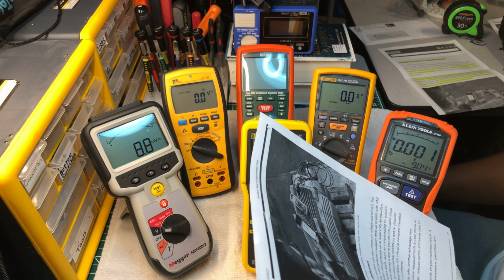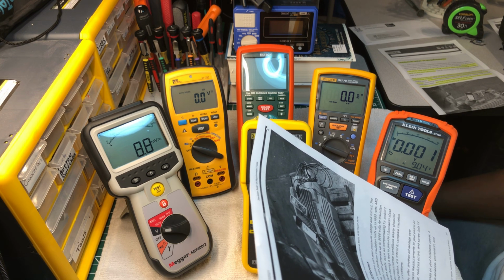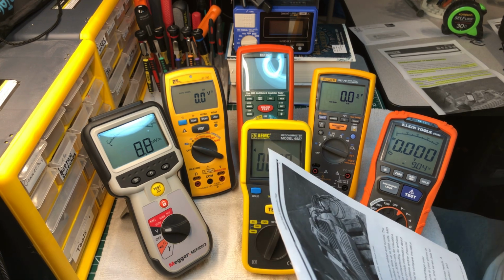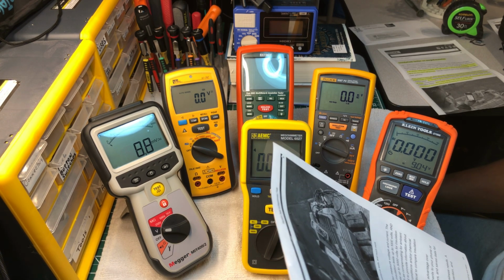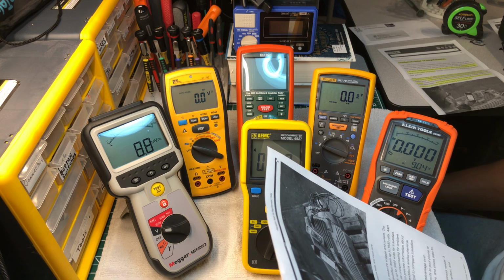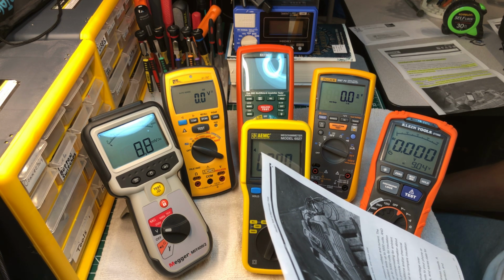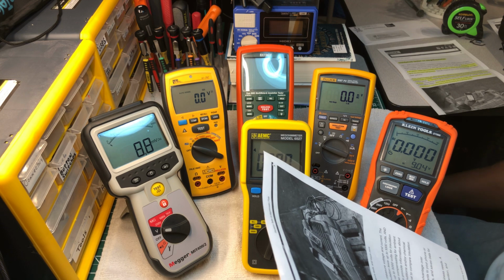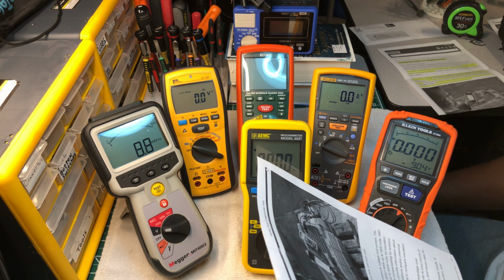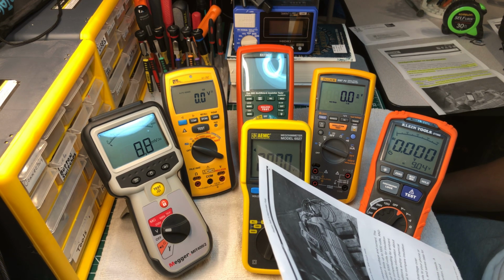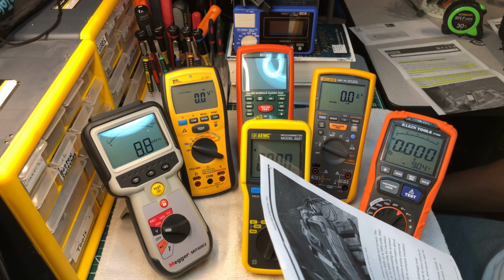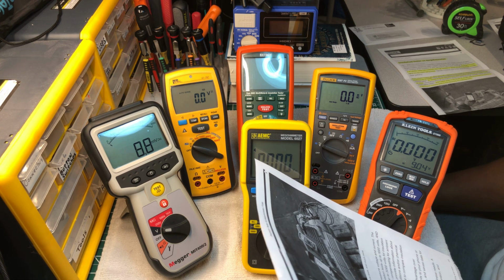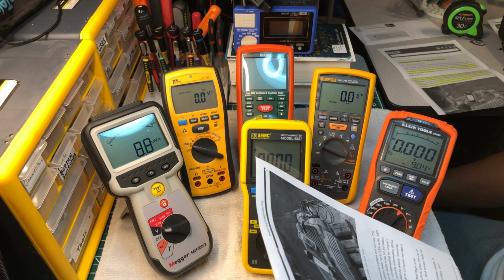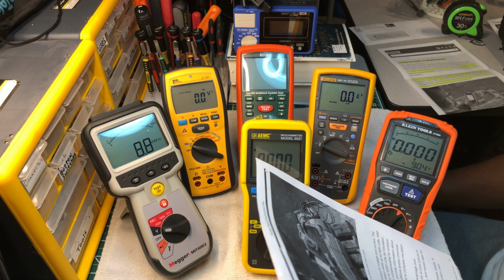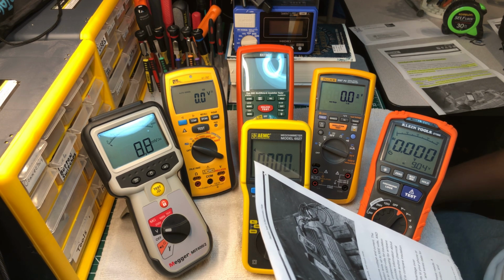Insulation testers can also perform more complex tests, such as compensating for ambient environmental conditions like humidity and temperature during a test, to provide information about how motors perform in changing conditions. Because environmental conditions and/or chemical contamination accelerate the rate at which insulation degrades, it's critical to compare insulation resistance test results that are corrected for different conditions.